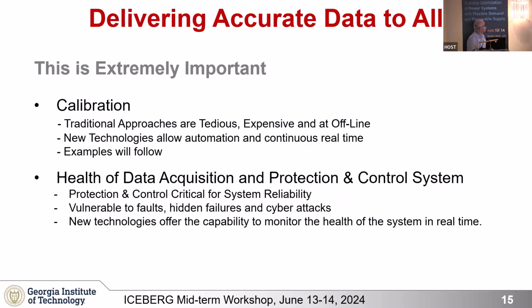Before we go there, we need to make sure the system is fully calibrated — that the data we get is valid and accurate, and that the system does not have any faults. For example, for data acquisition from merging units, we connect current transformers, voltage transformers, and sensors for temperature and speed to the input of the merging unit. If there is a short in that wire, we have a hidden failure in the system.